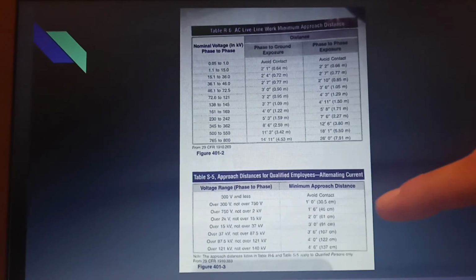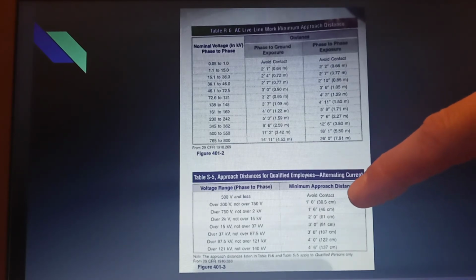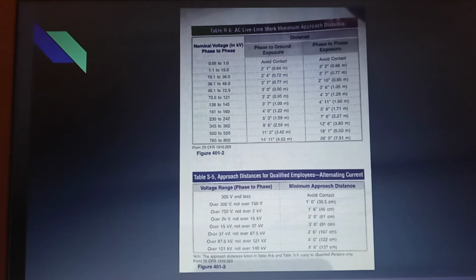And then down here on the bottom, right there, is the approach distance for qualified personnel, alternating current. The voltage range is, we'll do 300 volts and less because it's typically what I work with. And the minimum approach distance is to avoid contact. So if you go over 300 volts but not over 750 volts, the approach distance for qualified personnel is only 1 foot. So it's pretty small.